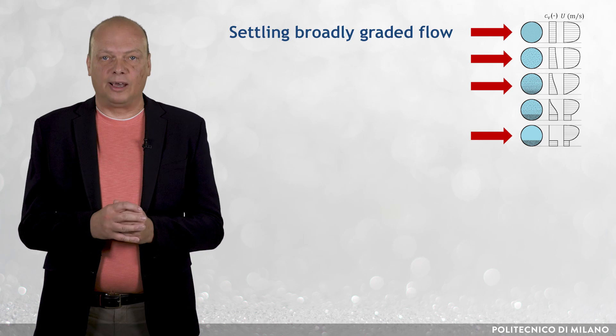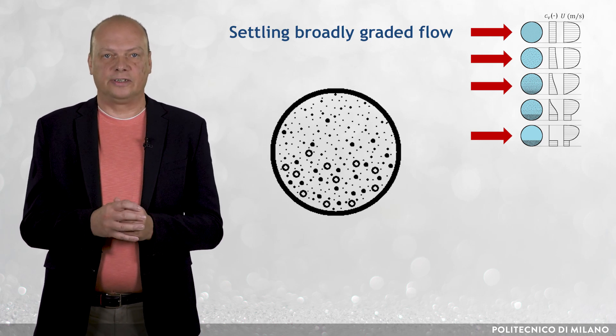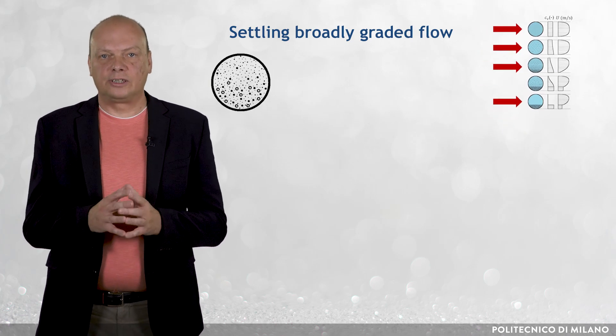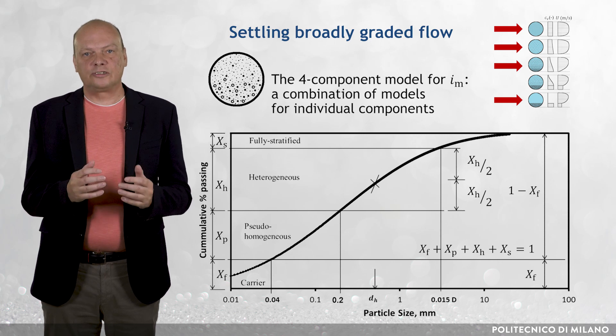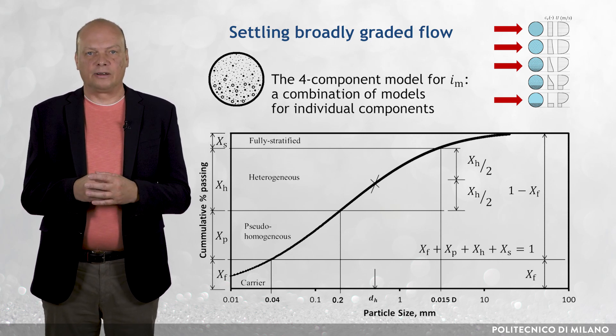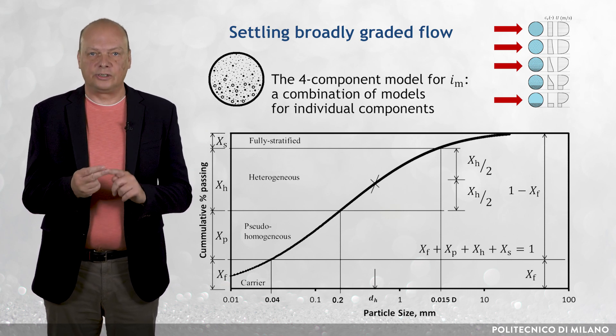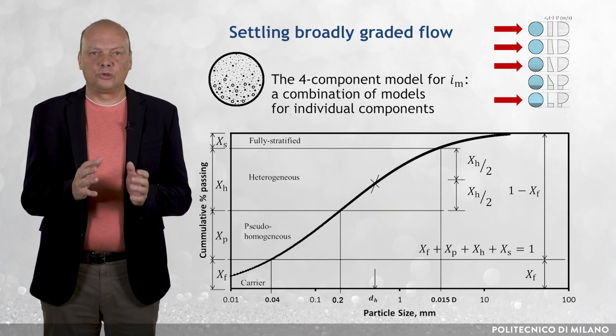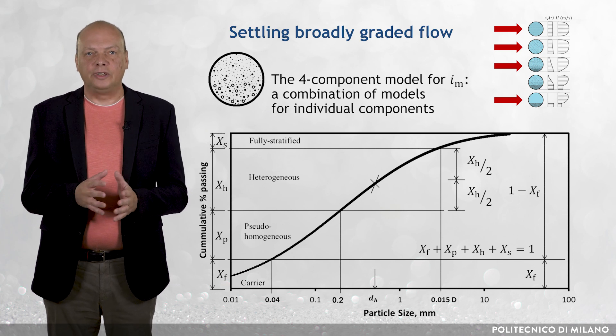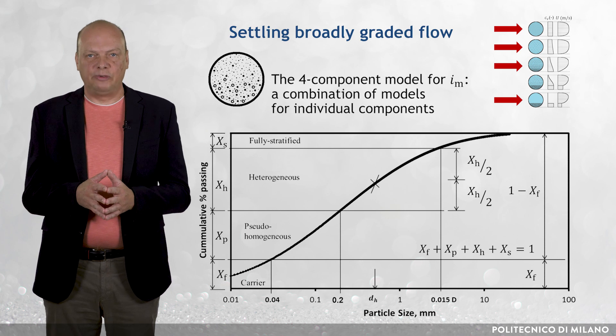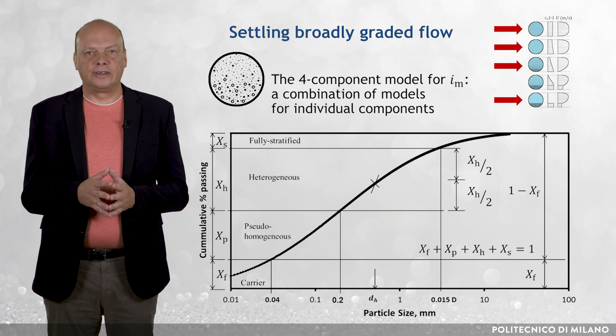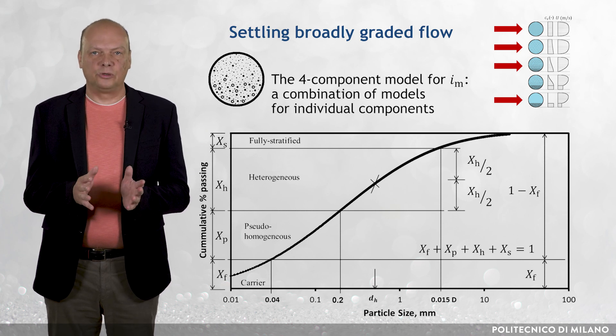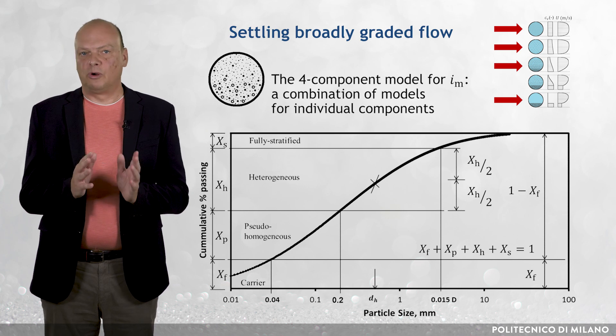Industrial slurries transported in pipelines often consist of a broad range of particle sizes that cannot be accurately described by any of the above models separately. A multi-component model, such as the four-component model, consists of a weighted combination of the models for pseudo-homogeneous flow, fully stratified flow, and heterogeneous flow, together with the Newtonian carrier fluid model. The solids are divided into size-delimited components, and the incremental contribution of each is evaluated according to one of the previously defined models. These contributions are then summed to give a prediction of the total hydraulic gradient in the pipe, making the component model usable with settling slurries of any grading profile.